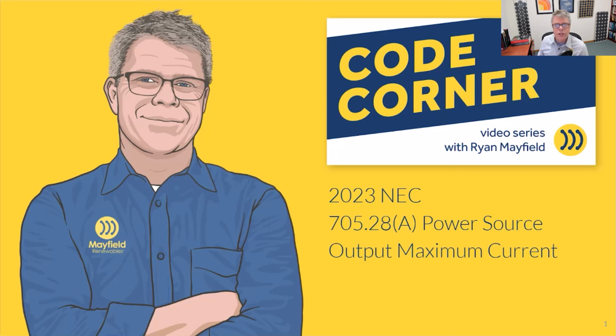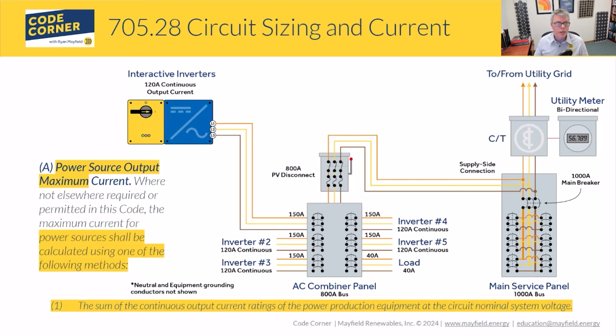The first one is probably what you're very accustomed to in terms of applying this. It's really the continuous output current rating of the power production equipment, at its nominal system voltage. So if we're looking at some PV inverters on the screen, for example, this will be the value listed in the manual on the spec sheet. What is that continuous output current? And that will be the maximum value.